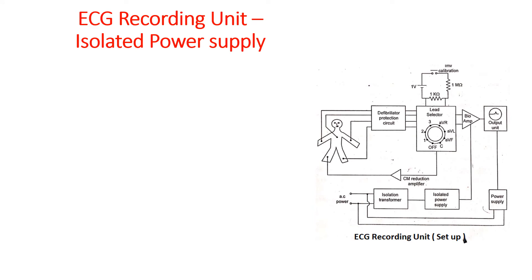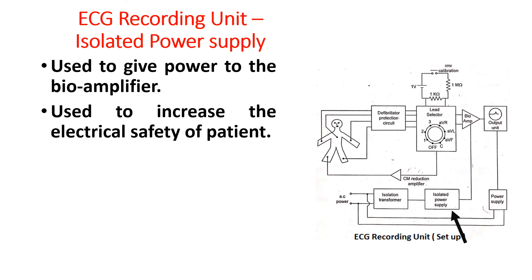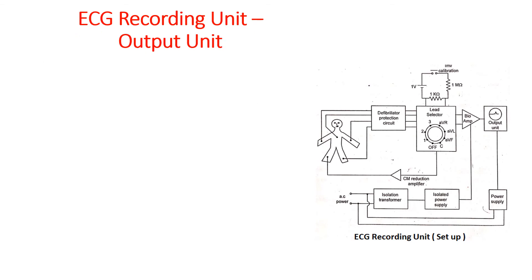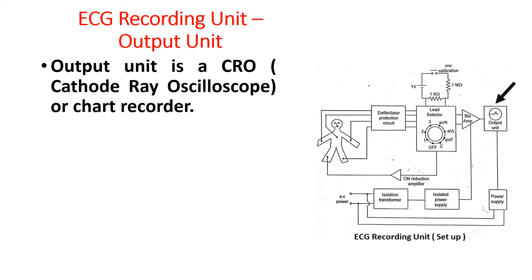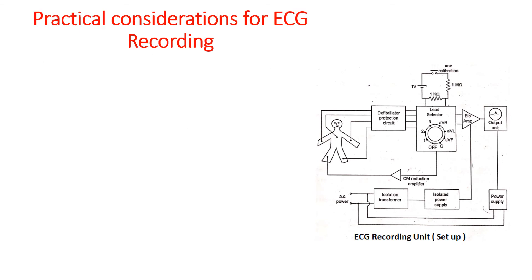An isolated power supply is used to give power to the bioamplifier. It is used to increase the electrical safety of the patient. The output unit is a CRO — that is, a cathode ray oscilloscope — or a paper chart recorder. In the case of a paper chart recorder, the power amplifier or pen amplifier supplies the required power to drive the pen motor. So far we have discussed about the ECG recording unit.